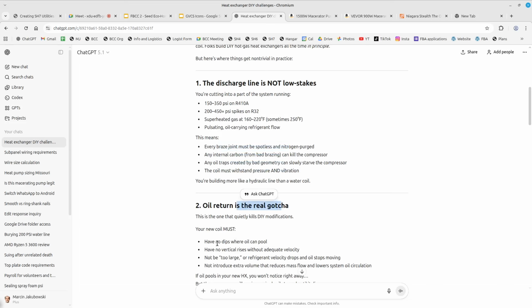So the oil return is the real gotcha. No dips, and this is exactly the issue that you've got to watch out for. The idea is no dips where oil can pool, because the heat pump has lubricant in it. There's oil in the actual compressor. So if you do not design this right, meaning that you have some low spots in your heat exchanger, then oil will pool there, and you'll break your compressor because it doesn't get lubricated. So you must make the system such that the coil could be a spiral going up, so that any oil that goes into the fluid lines drips back down into the condenser of the heat pump. In other words, the big challenge here is that your heat exchanger has to be above the heat pump.